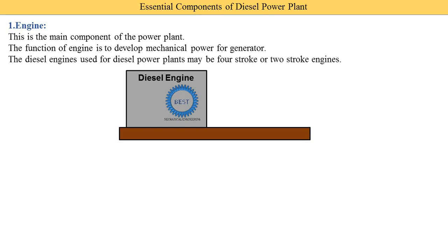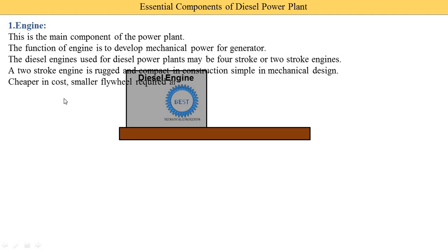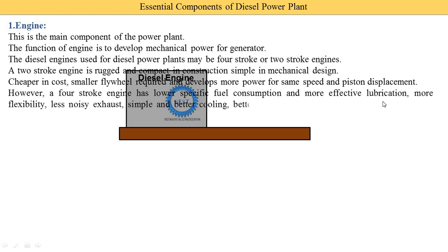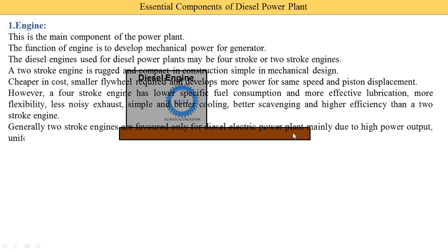Diesel engines used for diesel power plants may be four-stroke or two-stroke. Two-stroke engines are compact in construction and simple in mechanical design, cheaper in cost, require a smaller flywheel, and develop more power for the same speed compared to four-stroke engines. However, four-stroke engines have lower specific fuel consumption, more effective lubrication, more flexibility, less noise, simple and better cooling, better scavenging, and higher efficiency than two-stroke engines. We use the four-stroke engine in a diesel power plant because it has a number of advantages.